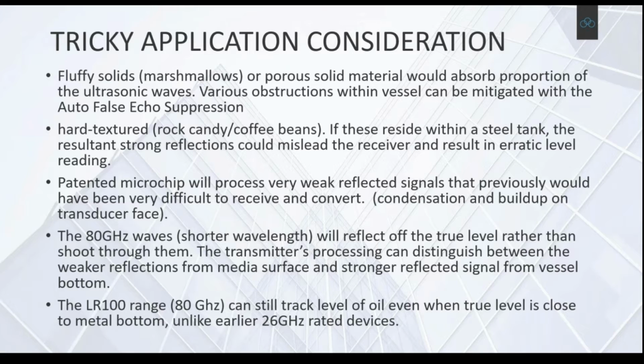You've got, say, rock candy and the like in a steel tank, then you've got basically like snooker ball reflections - the waves are bouncing, hit the surface and bounce off the surfaces of the tank, sides of the tank, and go back to that transducer. So there's no difference in the signal strength between what's reflected from the surface of that hard material or the sides of the tank. So it can give you unreliably high, unreliably low readings on a day-to-day basis.